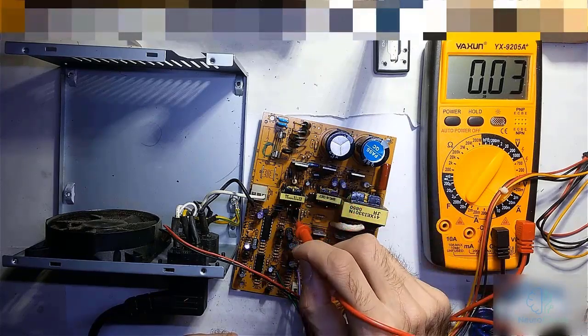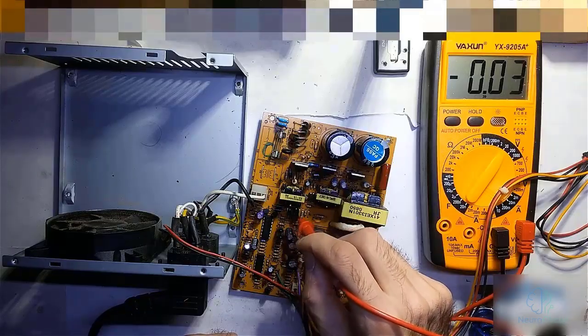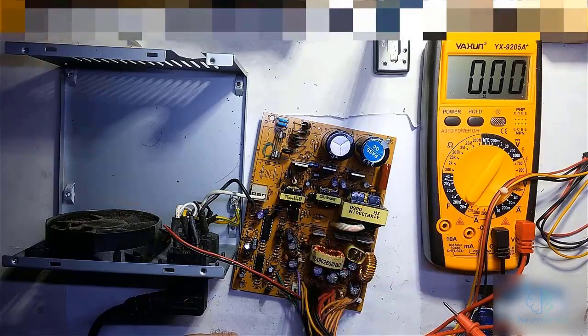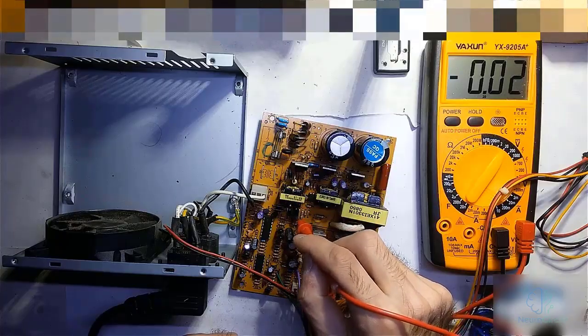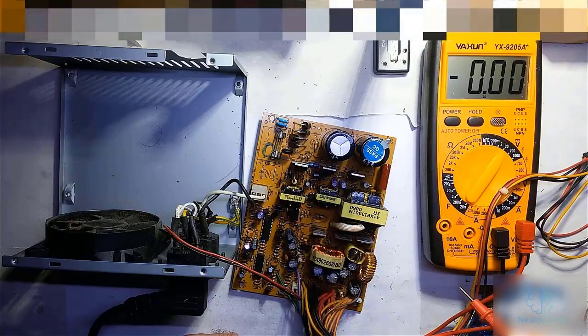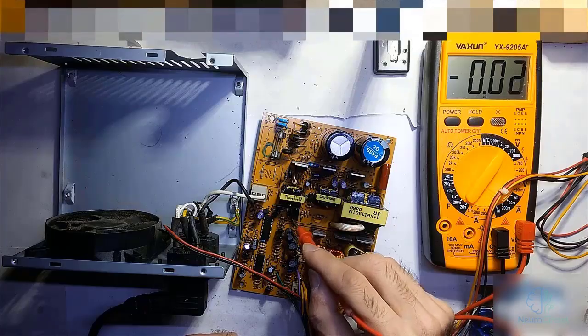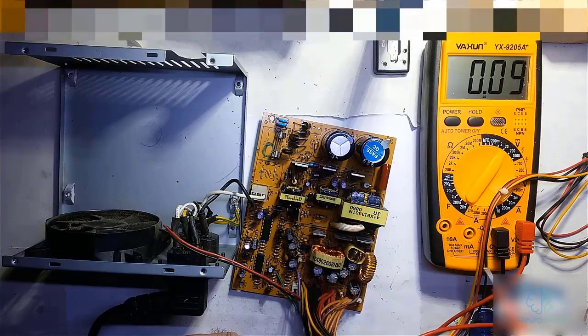Our final problem was with the diodes located here, connected to this transformer. Immediately after the transformer's output, there are two diodes, one large and one smaller. We tested them, found the larger one faulty, replaced it, and our standby voltage was restored.